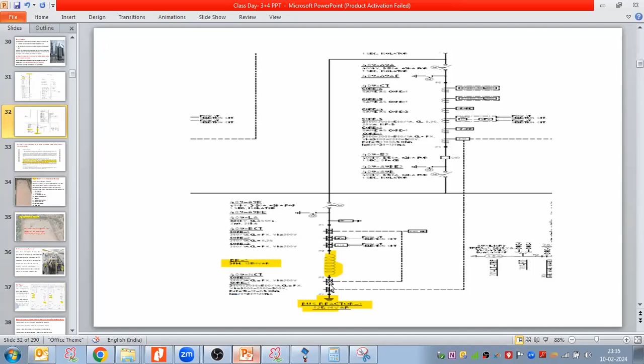See, we require NGR only for single pole auto-reclosing. If I have 3-pole auto-reclosing, like in the case of a bus bar where we have the reactor connected with the bus bar, then since there is no temporary fault on the bus, in that case my reactor would not require single pole auto-reclosing. Auto-reclosing here would always be 3-pole auto-reclosing (TPAR), so NGR is not required.